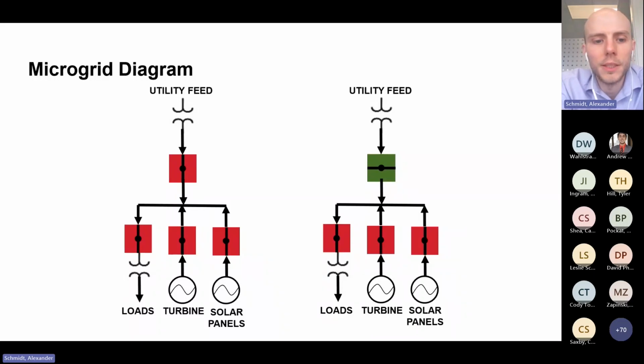Say you have a turbine and solar panels on your microgrid, along with loads at your site, like a hospital. In this case, you'd be doing what's called line interactive. Your solar panels and turbine would sync to the utility's 60 hertz AC waveform and push current into that grid. If your loads are less than your generation, you push power back into the utility, which is why it's so important to have a utility interconnect agreement. If loads are greater, the utility supplies the difference.